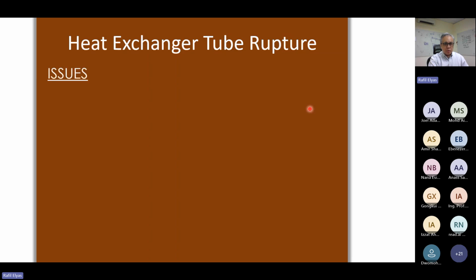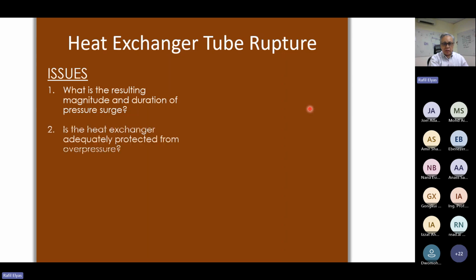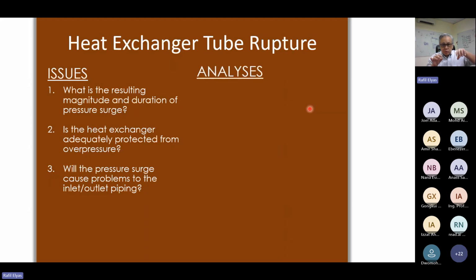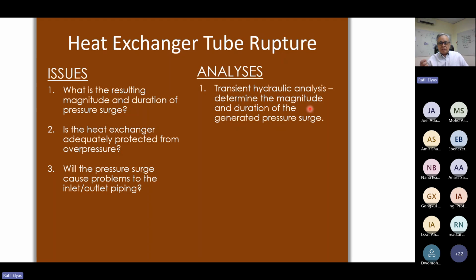Okay. So the first thing we need to know is the resulting magnitude and duration of the pressure surge, and also where in the shell it occurs. We want to look at the pressure profile as it traverses the shell. We want to know if this heat exchanger is going to be adequately protected from overpressure, and whether this will also cause issues with the inlet and outlet piping. So what kind of analysis do we need to do? Well, we need to do a transient single phase hydraulic computation.